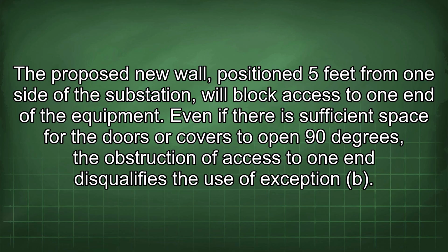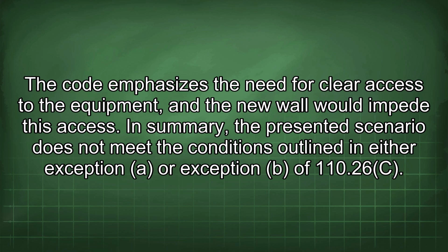The proposed new wall, positioned 5 feet from one side of the substation, will block access to one end of the equipment. Even if there is sufficient space for the doors or covers to open 90 degrees, the obstruction of access to one end disqualifies the use of Exception B. The code emphasizes the need for clear access to the equipment, and the new wall would impede this access.